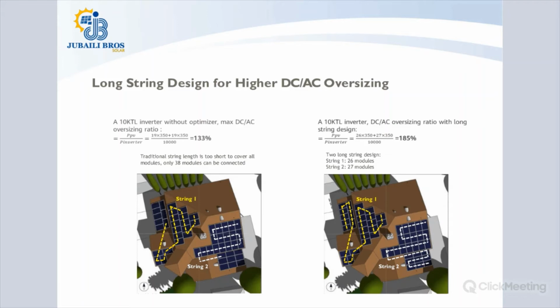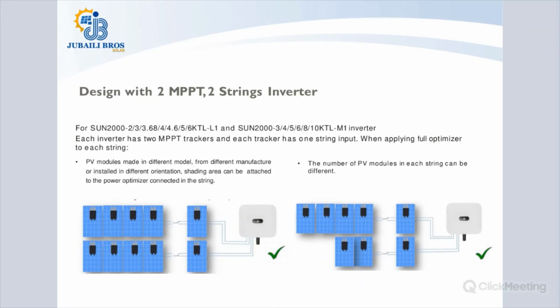And this will not only increase the DC to AC ratio, but of course, it will also reduce the cost of BOS. Because the longer the strings, the lesser the amount of stuff we use, like cabling and all that. So the BOS cost is also reduced. The DC to AC ratio is increased, mainly for areas where there is low solar irradiation. This system is absolutely necessary. So let's take a look forward.